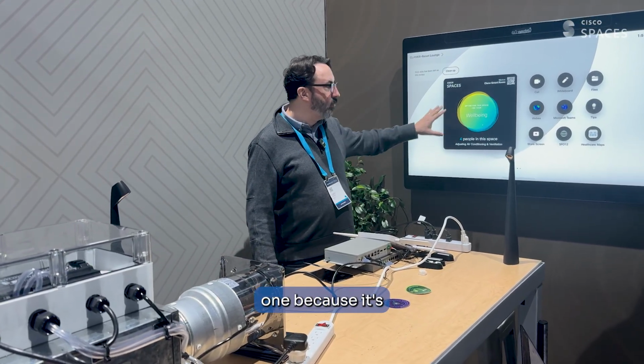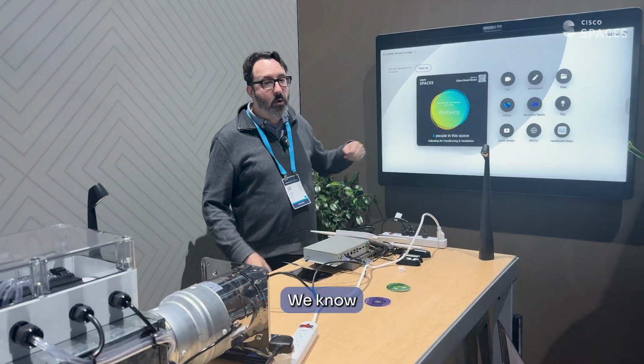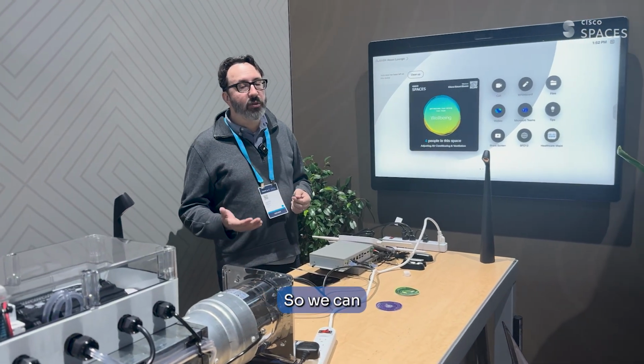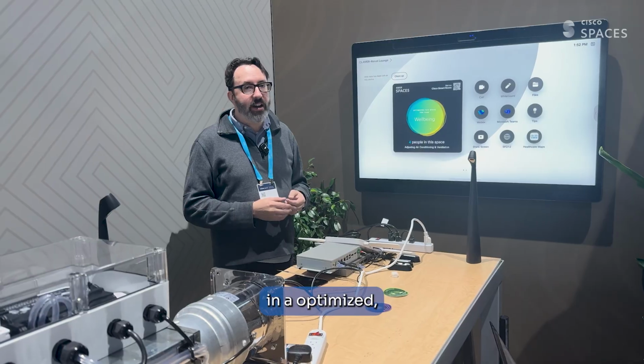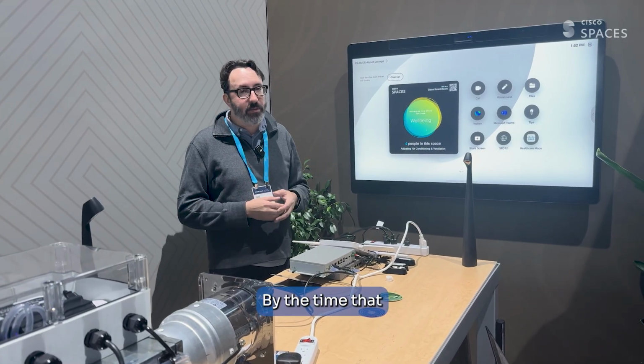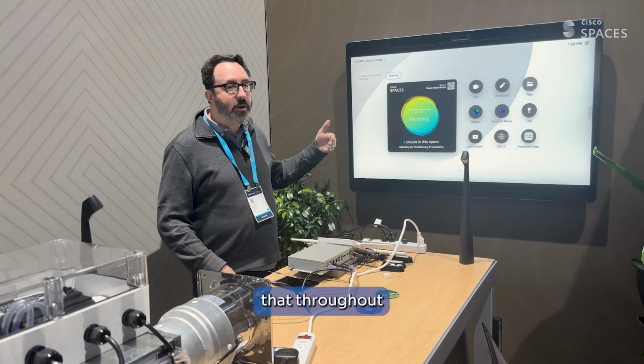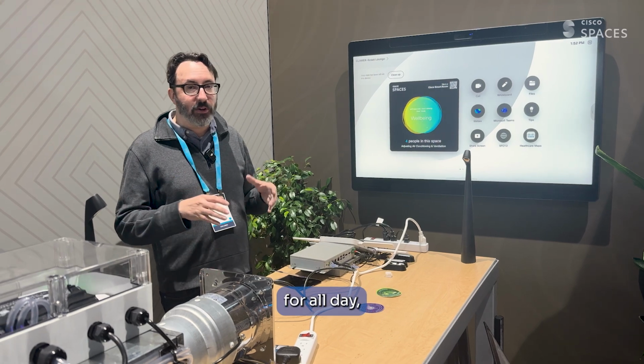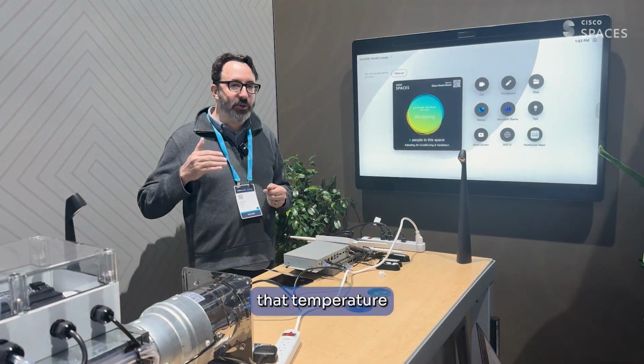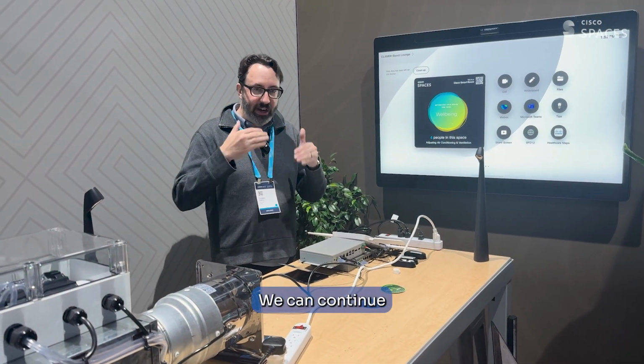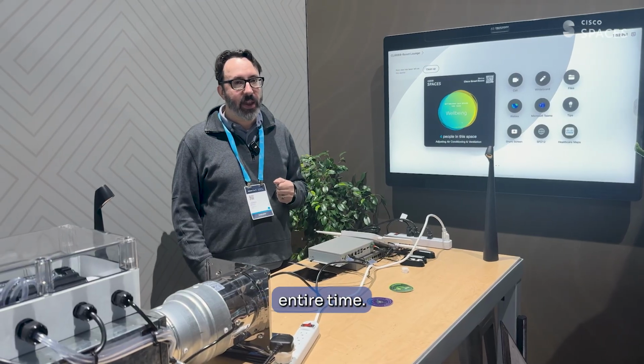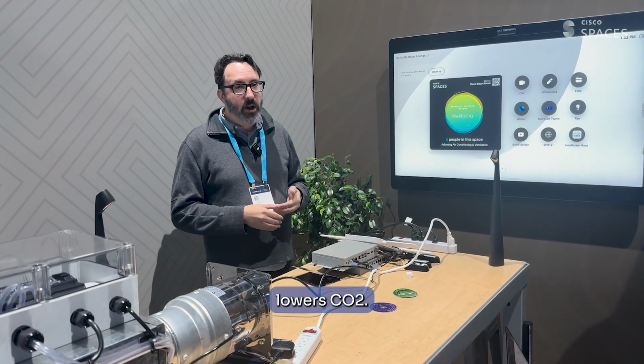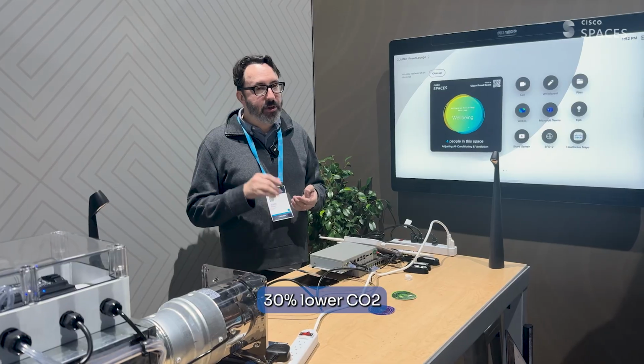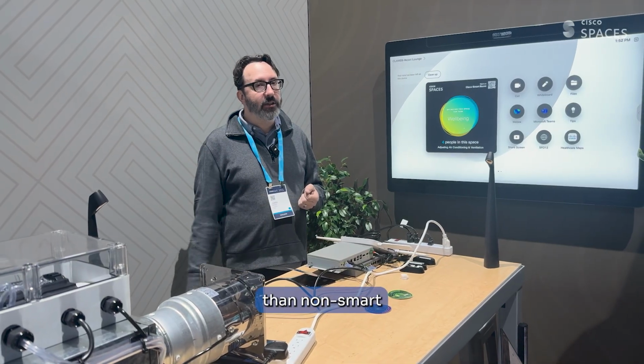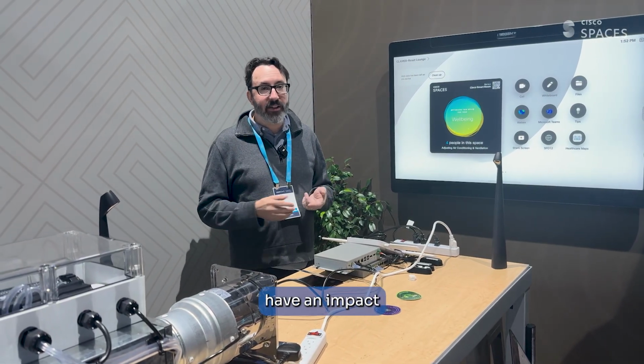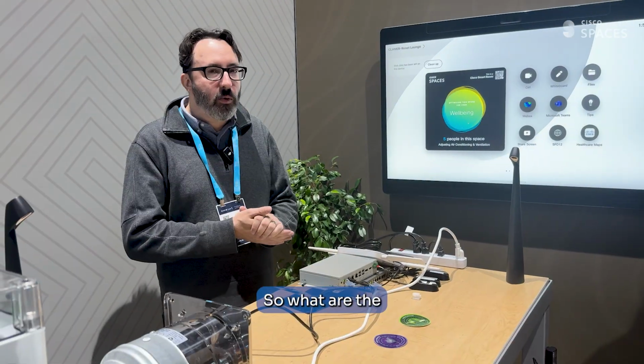With smart rooms, one, because it's connected to Webex, we know when your upcoming meetings are going to happen. So we can precondition a room so it's already in an optimized, comfortable temperature by the time that you come in, and we continue to monitor that throughout the meeting. So if you're in a room for all day, we never let that temperature get to that uncomfortable temperature. We can continue conditioning the entire time. That also lowers CO2. Smart rooms have on average 30% lower CO2 than non-smart rooms, which does have an impact on productivity and wellness.